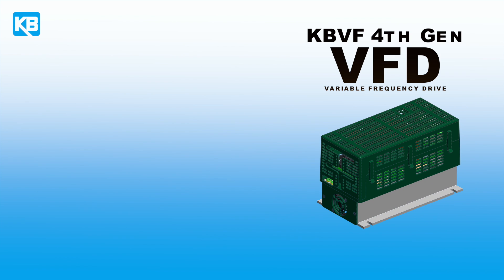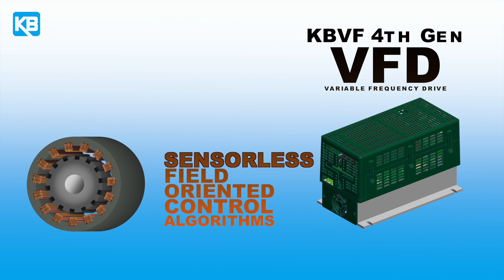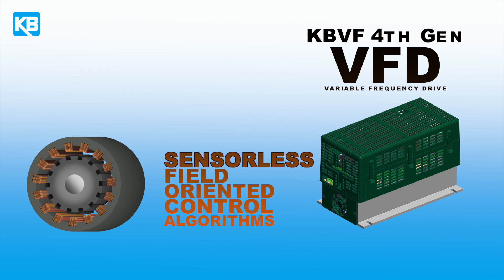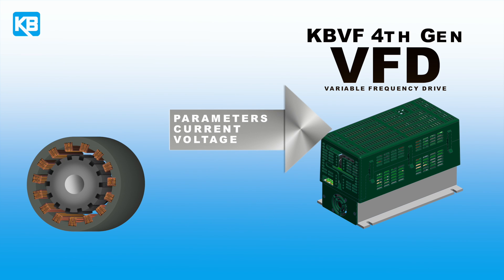So why are we talking about this? The KBVF fourth-generation VFD uses high-performance sensorless field-oriented control algorithms to control a PMAC motor. The drive uses the motor parameters, the current, and phase voltage measurements to estimate the rotor position.